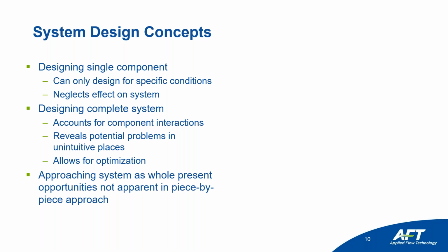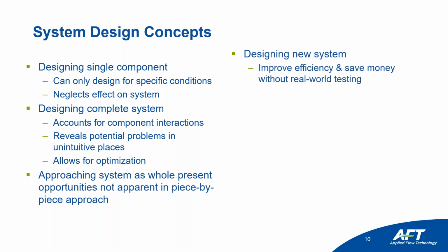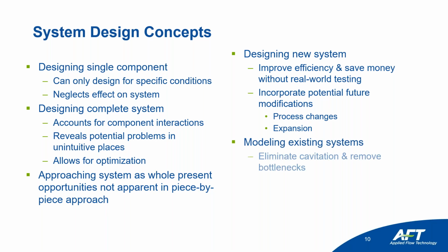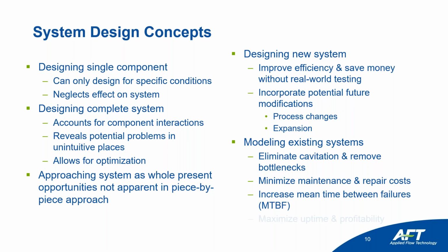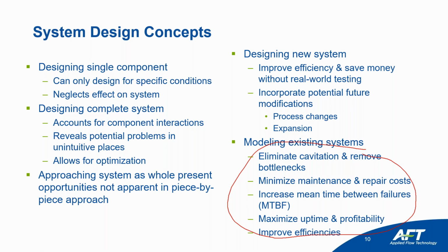Okay, if you approach the system as a whole, you can really get a good look at what's going on around you, rather than doing one piece at a time. If you're designing a new system, you can improve the efficiency of your system from the get-go and save money without doing any real-world testing. So that's a major advantage there. You can incorporate potential future modifications, process changes, and expansions, and analysis will help you figure out the impact of what's going to happen in those cases. If you're modeling existing systems, you can eliminate cavitation, remove bottlenecks, minimize maintenance and repair costs, increase mean time between failures, maximize uptime and profitability, and improve efficiencies. So if you're looking at the whole system, you can uncover all of these different benefits right here.